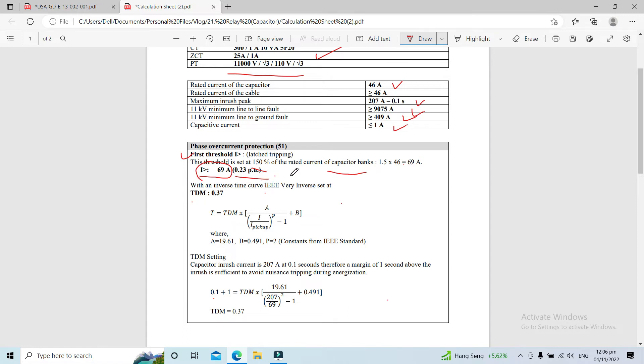The 0.23 per unit is derived by multiplying the pickup current of 69 by the CT ratio of 1/300. The curve selected is the IEEE Very Inverse curve, set on that particular characteristic.